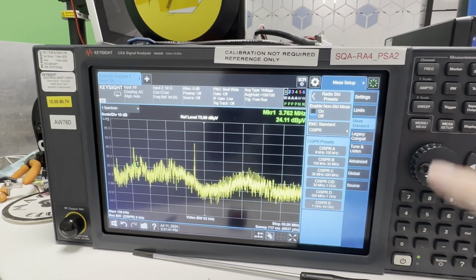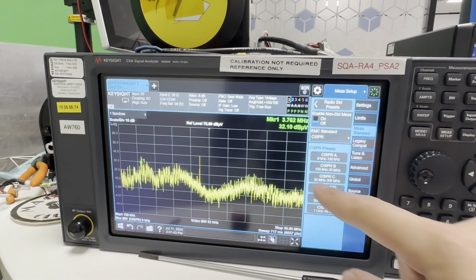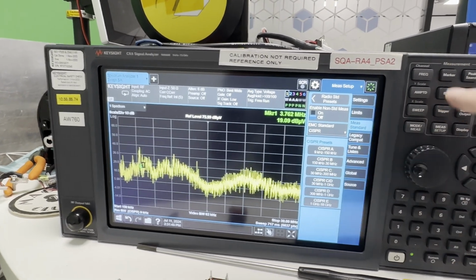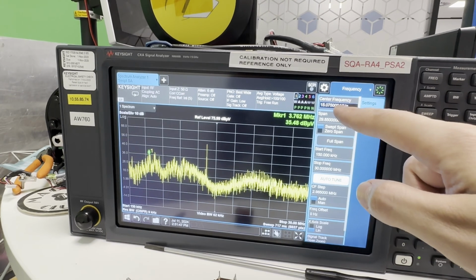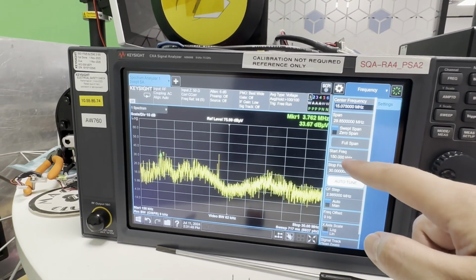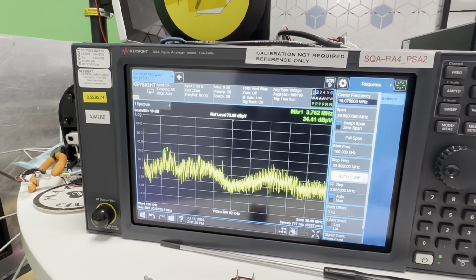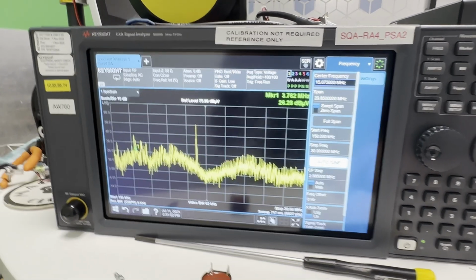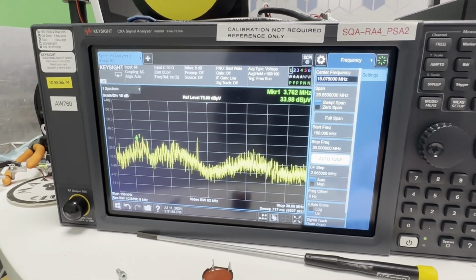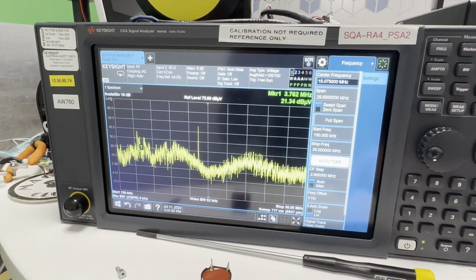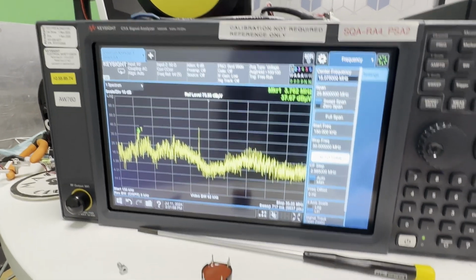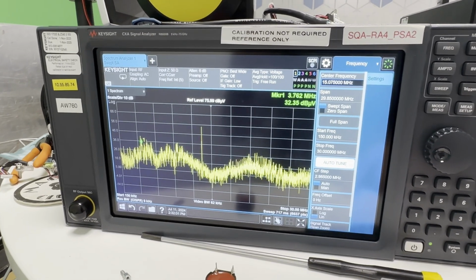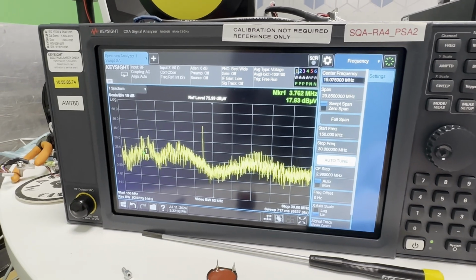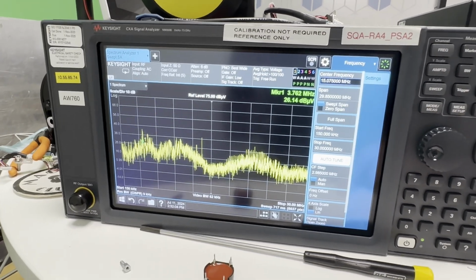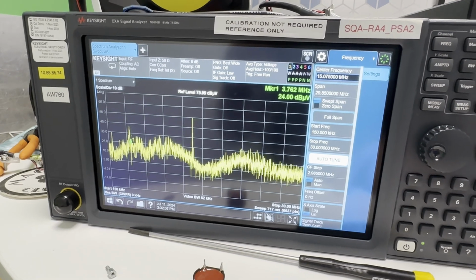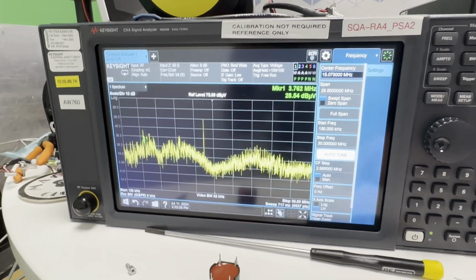If you didn't have the preset, it's very simple. The first thing you would do is set up the frequency from 150 kilohertz to 30 megahertz. That is a typical frequency range for class B CISPR 32 and CISPR 22, and basically the conventional conducted emissions on AC.